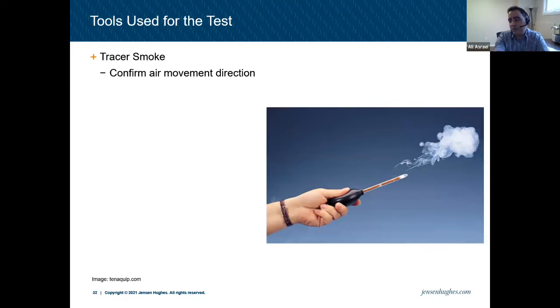The other thing that you can use is a tracer smoke. This is in the National Fire Code. It's permitted if you want to see the pressure from a pressurized area coming to the floor area. So you can use this, and you can see the smoke moving towards your floor area. So basically, if you have a pressurized stair and keep this device close to the stair, the smoke should travel towards your floor area, so it cannot get into the stair. This is a way. When we get to the test and maintenance procedure, you'll see that's one of the ways permitted by the National Fire Code.